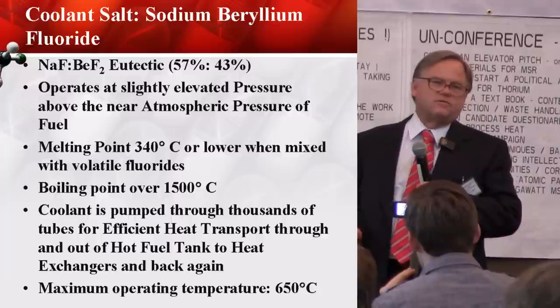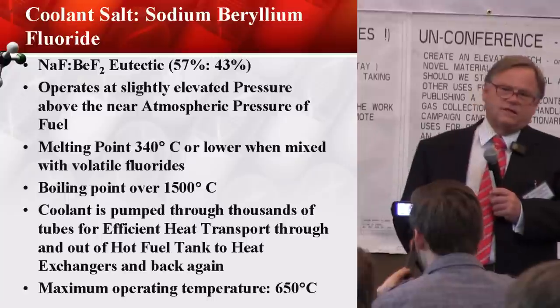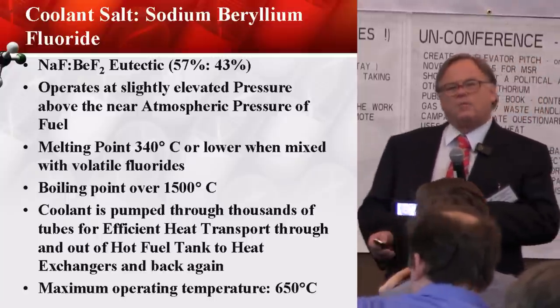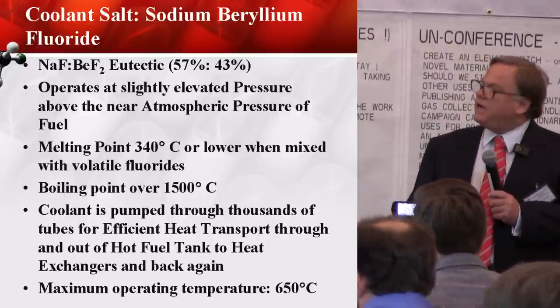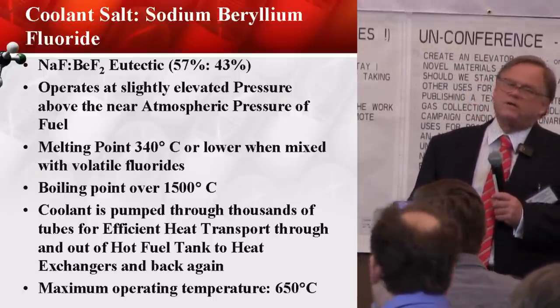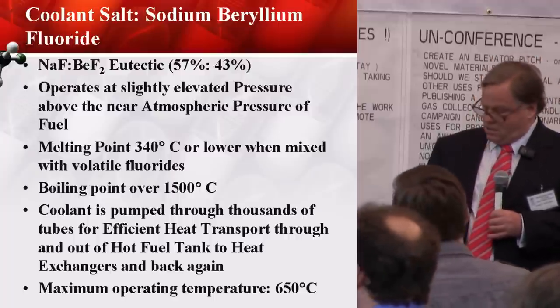We have thousands of tubes in the tank, and the fuel is essentially sitting still in the tank, although we can pull out the fission gases as they're produced, and we separate out the fission gases and trap the fission products as they are generated. My temperature is around 650 degrees max. It'll go hotter, but I don't want to stress my materials. I want to keep things within the materials book.